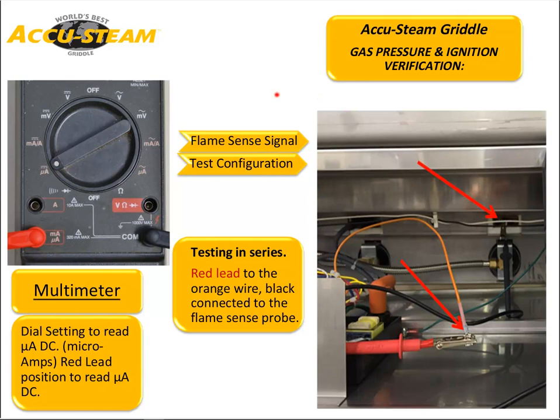They won't go into ignition lockout unless there is a flame sense issue. You will power the unit on, read the flame sense. Griddles will be slightly lower than our steamers. You'll typically see something between 2.4 to 4 DC microamps. It will start low, and as those burners get warmer, it will increase that flame sense signal. If the flame sense signal is too low for any of our pieces of equipment, they will close the main valve, and then signal ignition lockout.